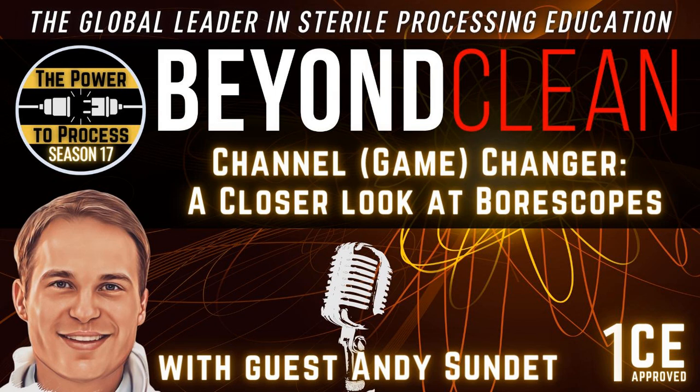We've talked about this before, but this really came from a completely different sort of perspective, I think, Hank. And it's more about the ownership of this equipment, which is very much in theme as we wrap up this season. And I love the four D's, just making sure that you know what to be looking for when inspecting scopes using the Borescope, those four D's being debris, damage, discoloration, and droplets, because moisture is a killer to these electronic instruments, especially if it can get in there, get at the wiring, and start eating away, corroding, or just simply short-circuiting the technology.